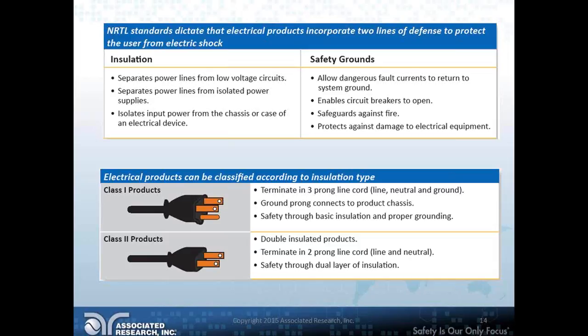Now, if you've ever dealt with a Class 2 product - and everybody listening to this has - do you have a smartphone? Do you have an iPad? Do you have a laptop? Well, all of the adapters that plug into the wall, you'll notice most of the time, there are some exceptions, they have 2 prongs. Why? Because there's no ground pin. So what they do is use a layer of dual insulation - double or reinforced insulation instead of grounding as your extra means of protection. So this terminates in a 2-prong cord, and you get that safety through that double layer of insulation.